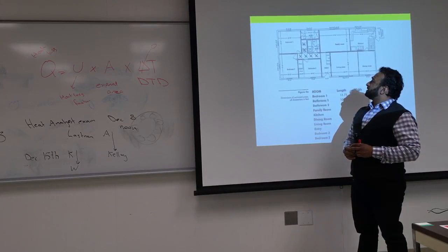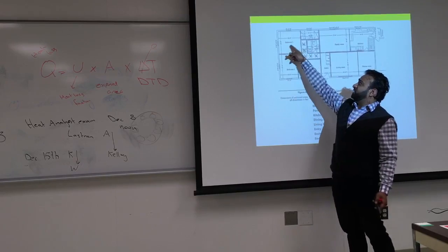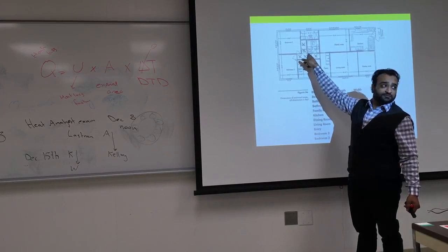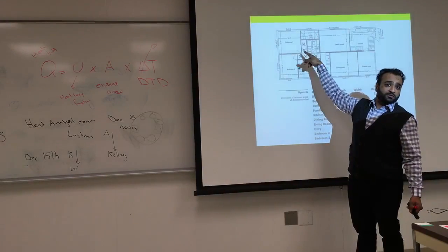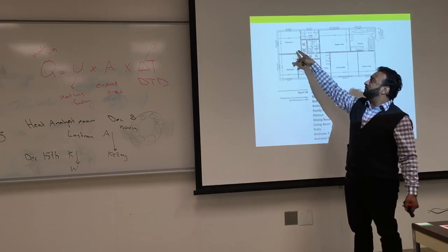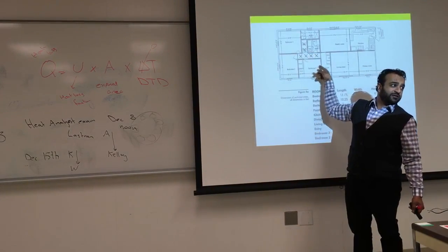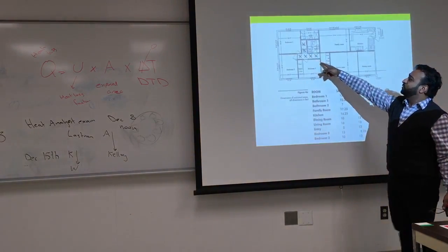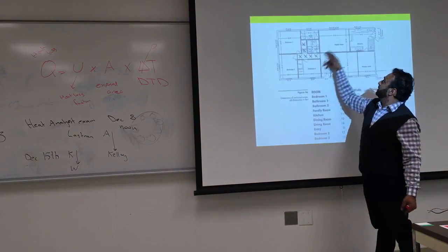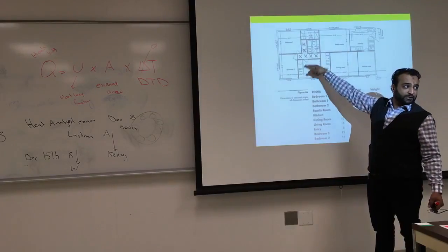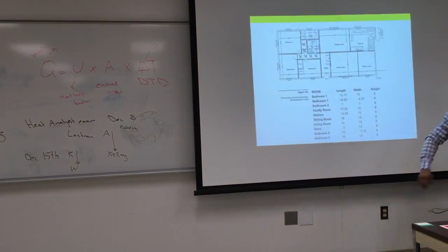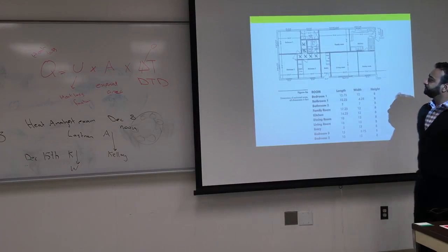And the rationale is, if you're going to heat this section with only one zone, you're probably going to put your thermostat here, for those 2 rooms. So until it gets to 65 here, probably it's around 67 in these rooms. So you probably have two zones. In my opinion, I'd make this house with 2 zones. This one zone will have its own thermostat, and another thermostat over here, or maybe even over here.